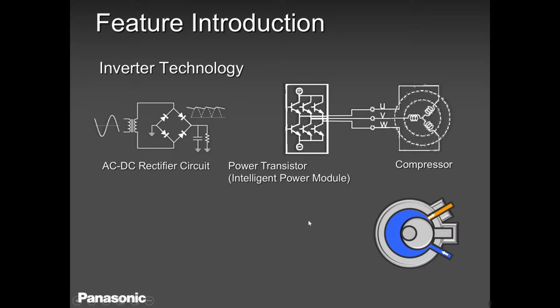So what is this inverter technology all about? It's just a single board, and trust me, it's not too complicated. AC comes in, goes into this rectifier circuit. From the rectifier circuit, it goes into this intelligent power module where AC is converted to DC, and then DC is converted again to AC three-phase. AC three-phase, and that's how this compressor is regulated between U, V, and W. All the time you will get a balanced voltage there. Okay, and we'll talk about this, how to find out if the board is a problem or the compressor is a problem, in my next slides.